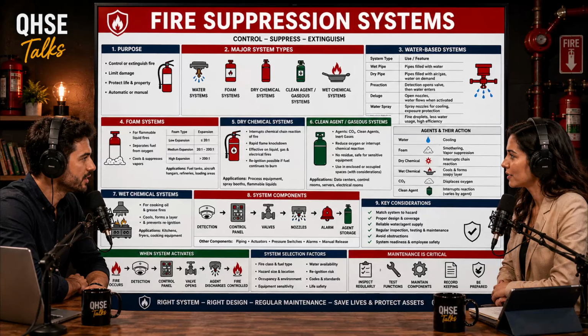Let's start with carbon dioxide or CO2 systems. How did these differ from sprinklers? Well, carbon dioxide extinguishes fires primarily by physically displacing the oxygen in the environment. These systems store liquid CO2 in high-pressure cylinders. They can be engineered for total flooding, where they literally fill an entire enclosed room with CO2 gas, or local application, where they discharge directly onto a specific piece of equipment.